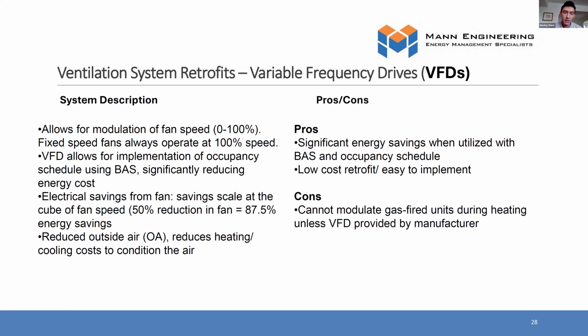And not only does the VFD provide electrical savings on the fan, but more importantly, by limiting the amount of unconditioned air you're bringing into the building, that greatly reduces the heating or cooling costs of that system. Think about it in the middle of winter: if you're bringing in minus 20 degree air into the building at 100% fan speed, all that cold air has to be heated, which is cost. So if you can reduce the amount of fresh air you're bringing into the building, that greatly reduces the cost of heating or cooling.